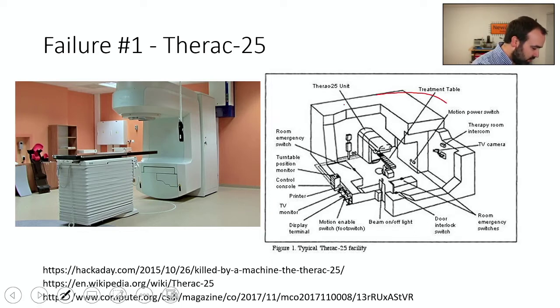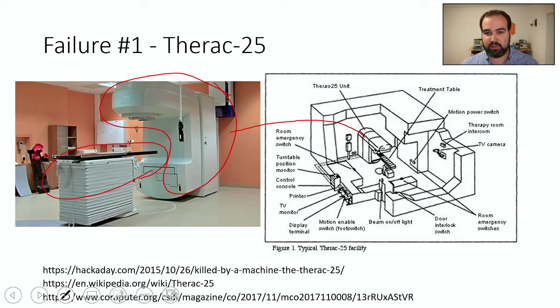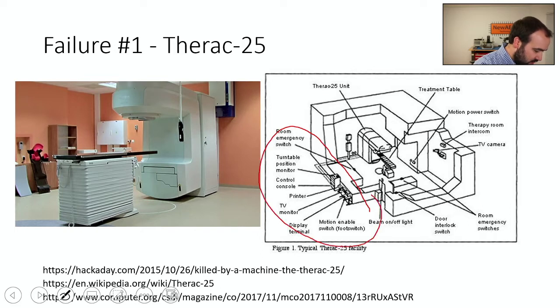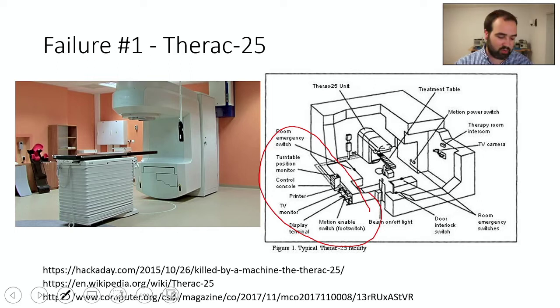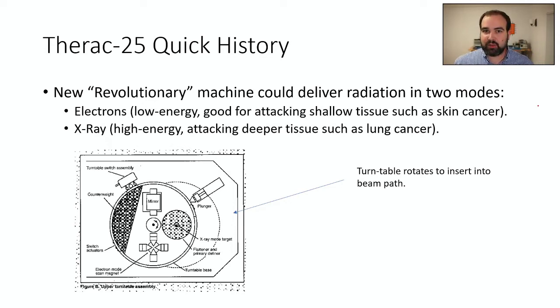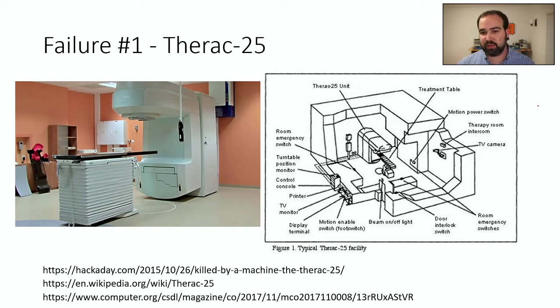In a typical treatment room, you have the THERAC-25 unit itself — a large machine — with a patient lying down on a treatment table underneath it, aligned to the machine. Because of the radiation, the operator isn't actually in the room; they're behind a shielded room observing. There may not be a direct connection to the machine, so some sort of remote control is needed. The THERAC-25 was a revolutionary new design that delivered two types of radiation to the patient.